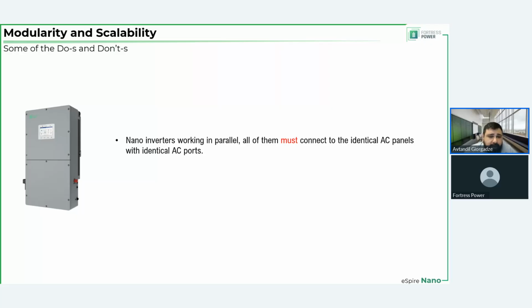I'm going to give you an extreme example. Let's say you have a generator and you have some inverters without the batteries and some inverters with the batteries. Even the inverters without the batteries will connect to the generator AC output, right? Because that's the rule. They all need to detect the same AC signal. Otherwise, you might encounter faults and not that great of a user experience. So please keep that in mind.